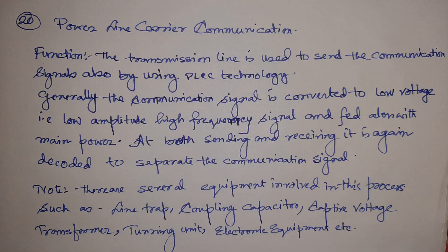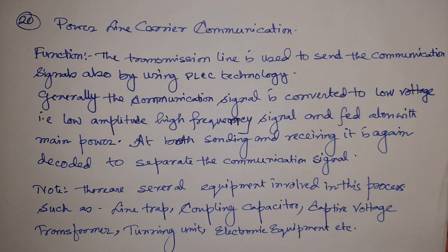Several filter and electronic arrangements are used to carry out power line carrier communication. The equipment used includes a wave trap or line trap, coupling capacitor, capacitive voltage transformer, tuning unit, and other electronic equipment. However, this is an older technology; nowadays OPGW — optical power ground wire — is used, where fiber optic cables are run through the shield wire. The communication signal is sent through the fiber optic cable, while the outer shield wire acts as the lightning protection element.